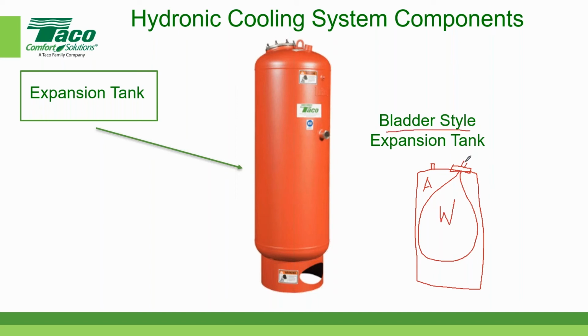So this is connected to a piping system. We kind of make a little piping system over here, and then we'll say the pipe runs past us in the system. And then as the water expands as a function of temperature, it goes into the bladder, and then it's held in place by the air cushion that's around there. So those are the basic components of a bladder-style expansion tank. So that's a major component.